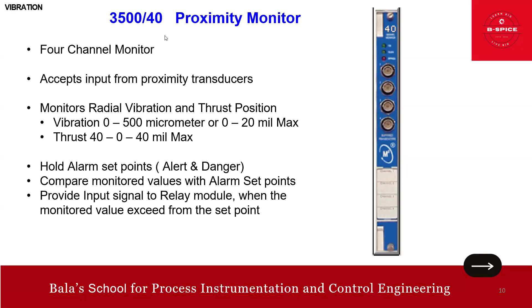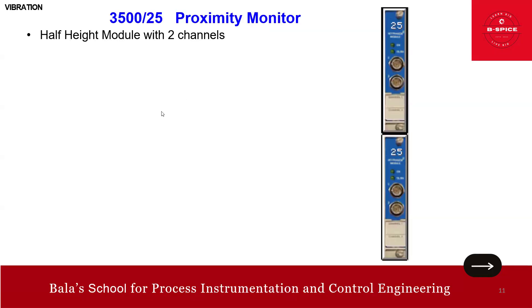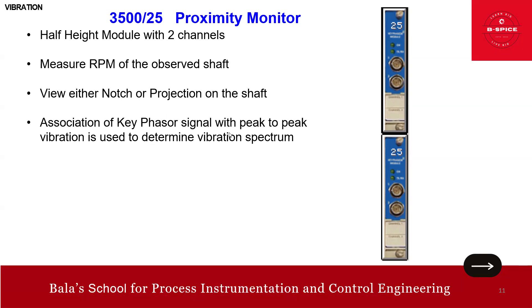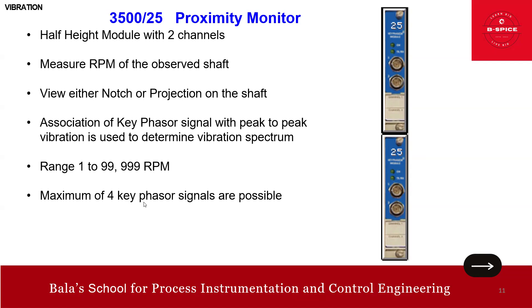Module 25 is the key phasor monitor — a half-height, two-channel module that measures RPM of the observed shaft using either a notch or projection on the shaft. It associates the key phasor signal with peak-to-peak vibration to determine the vibration spectrum. The range is 1 to 99,999 RPM, and a maximum of four key phasor signals are possible. It also provides buffered outputs.